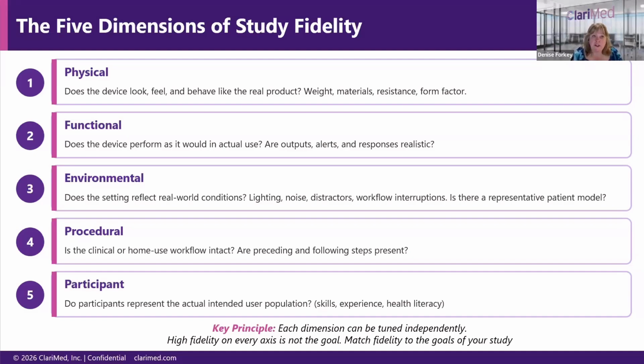For instance, if you're trying to determine how a user can interact with an emergency ventilator that's going to be used in an ambulance, then you want to have some studies along the way that look at whether they can do that in a constrained environment, with more noise and vibration in an emergency situation, as opposed to always on the bench or in a nice conference room without any environmental factors.